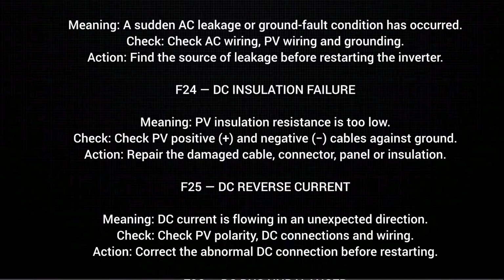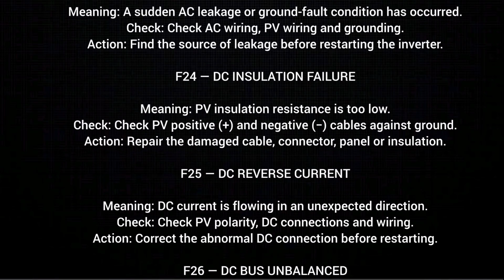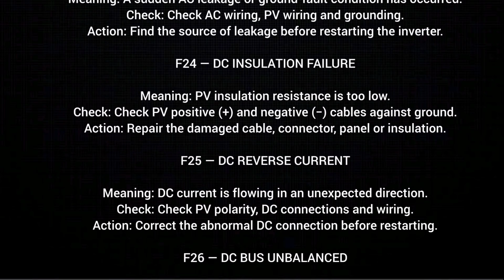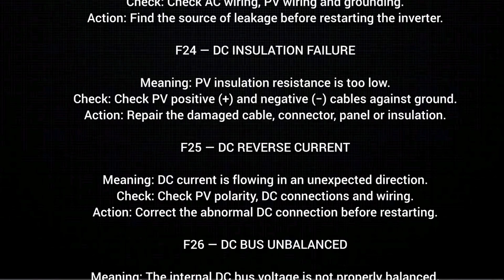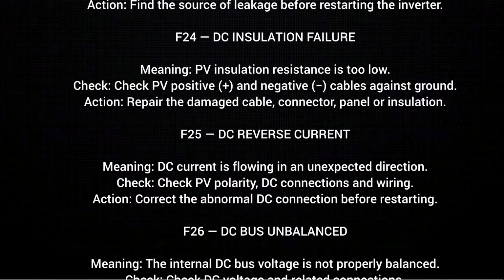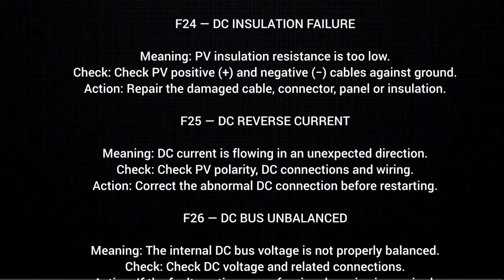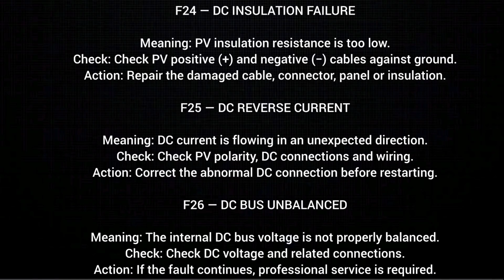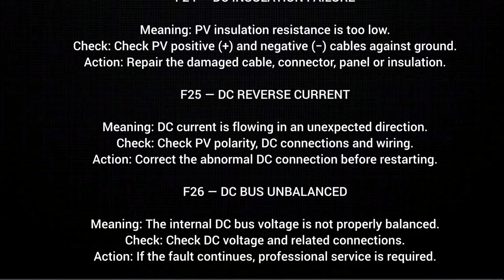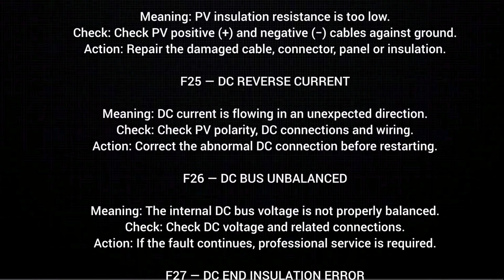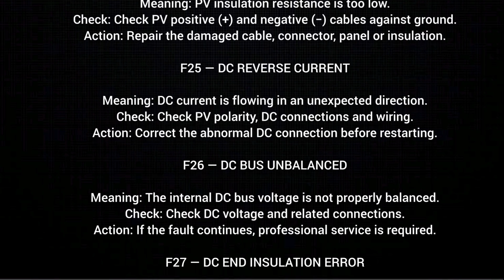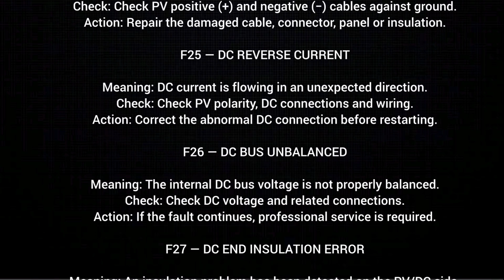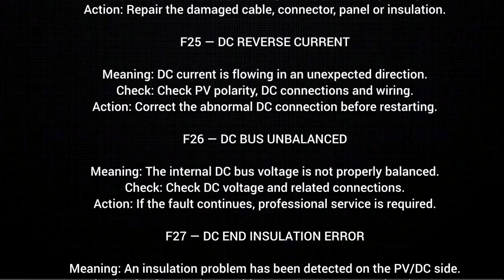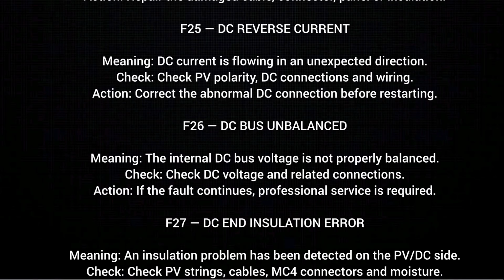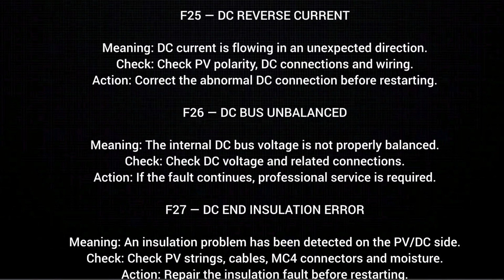F24. DC insulation failure, meaning PV insulation resistance is too low. Check. Check PV positive and negative cables against ground. Action. Repair the damaged cable, connector, panel or insulation. F25. DC reverse current, meaning DC current is flowing in an unexpected direction. Check. Check PV polarity, DC connections and wiring. Action. Correct the abnormal DC connection before restarting.